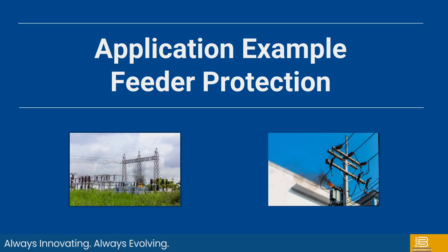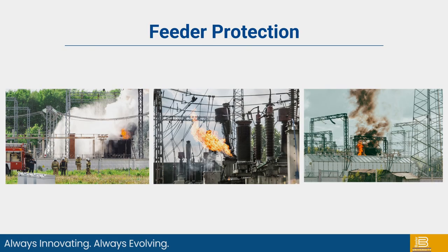So the first application example is feeder protection. Feeder protection is used to isolate feeders and minimize damage to equipment. Feeders can be used in transmission systems, distribution systems, data centers, industrial facilities, hospitals, office buildings, along with other applications. This protection also tries to minimize the loss of power to the system and only isolate the smallest portion of the system to minimize the effects on the system.